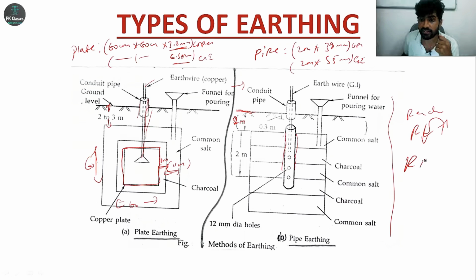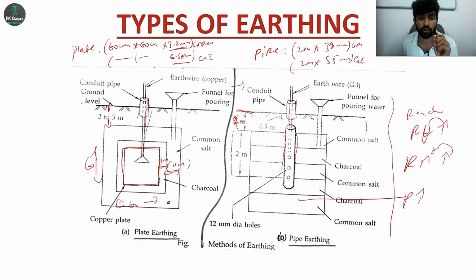If the resistance increases, fault current will not go directly to the earth, and if you touch the body of the equipment, you may get shock, right? That's why the charcoal, salt and then funnel for pouring the water they placed, right? Next there is an earth wire. Earth wire is for connecting the electrical appliances, and conduit pipe is for the passage of earth wire. Here there are 12 mm holes so that the electrode makes more contact with soil inside as well as outside. See here, pipe earthing is more efficient compared to plate earthing because it is in more depth, and whatever the short circuit current, fault current directly goes to earth and then maintenance free.